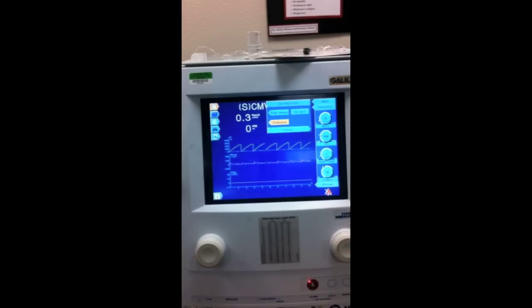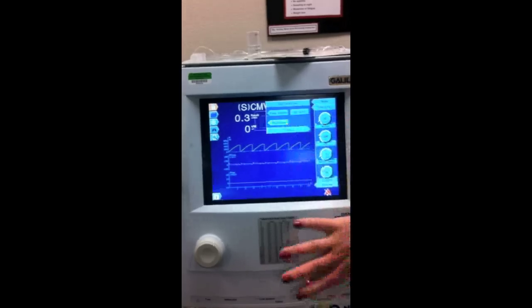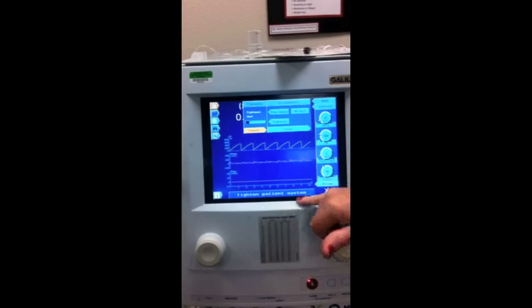All the tightness test is, is a leak test. It's going to test the integrity of the circuit to make sure there's no leaks in it. So it's just what it's called. So you go to there, push it, tightness test. Now it says tighten patient system. What that means is go like this. Close it off. Once you do that, it knows you did it. Pay attention to the blue, tighten patient system.